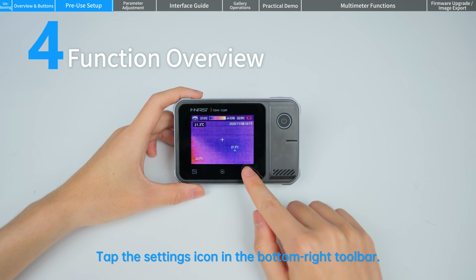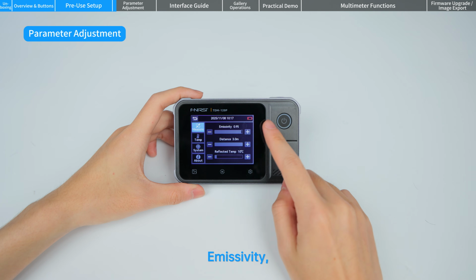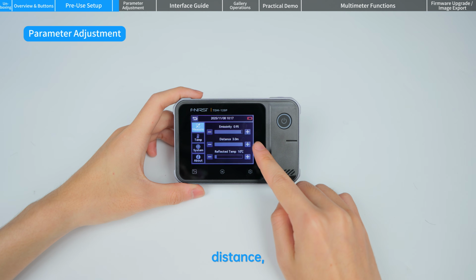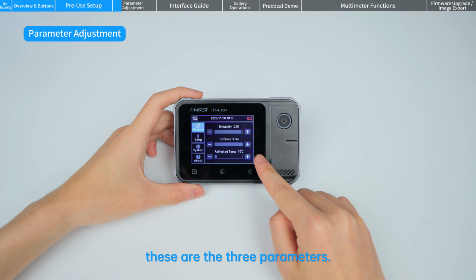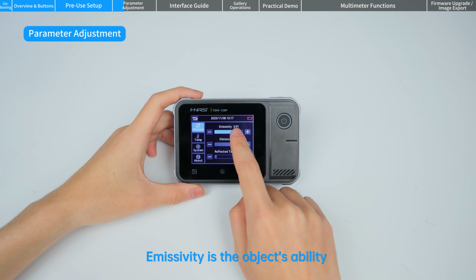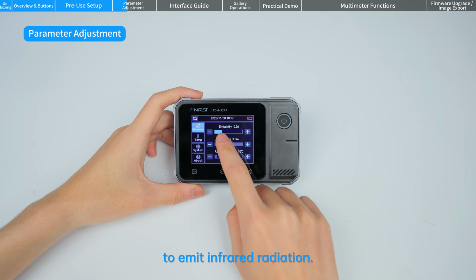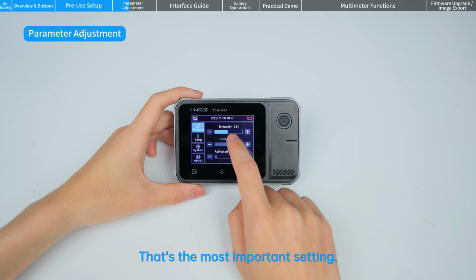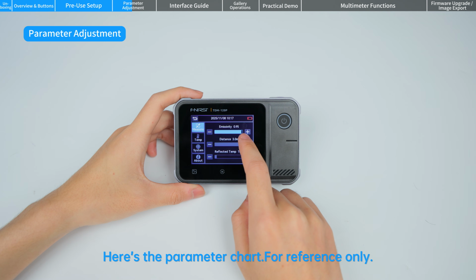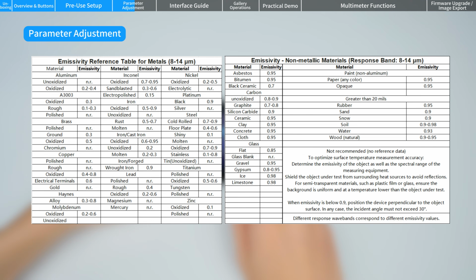Tap the settings icon in the bottom right toolbar. Emissivity, distance, reflected temperature, these are the 3 parameters. Emissivity is the object's ability to emit infrared radiation. That's the most important setting. Here's the parameter chart, for reference only.